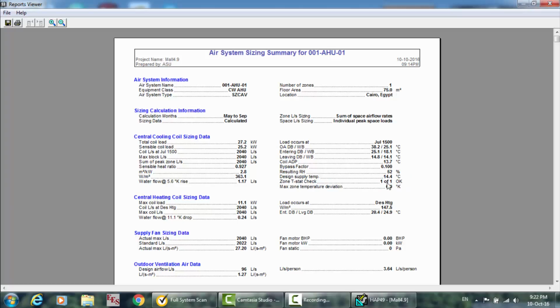Okay, zone T-stat check. This is 1 of 1. Okay, this is the throttling range. Remember that there is a throttling range. We want the temperature inside the room 24, and with a throttling range of 1, this means that you will have 24 degrees Celsius, and it is allowable that the temperature inside the room increases by 1 degree to reach 25. Then the HVAC system starts again. Okay, so it is okay. 1 of 1, the zone number 1. Okay, the HAP software will apply the throttling range as we did. So the maximum temperature of the zone will be 25, not more than this temperature.